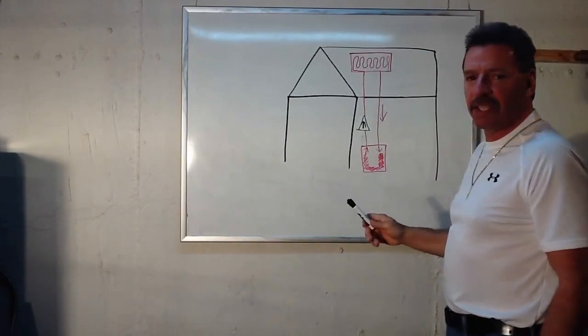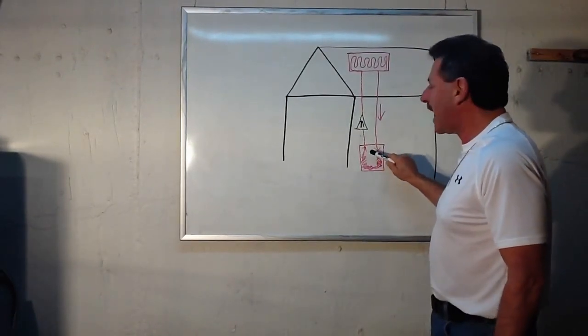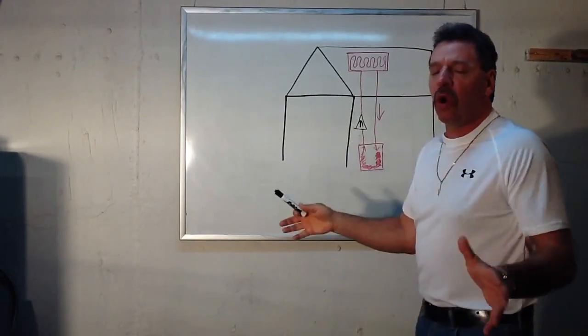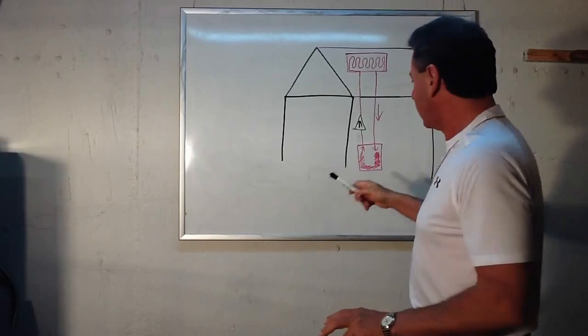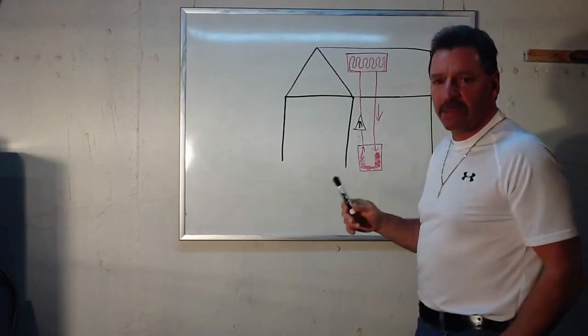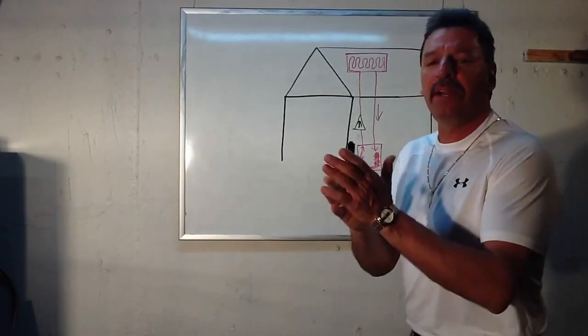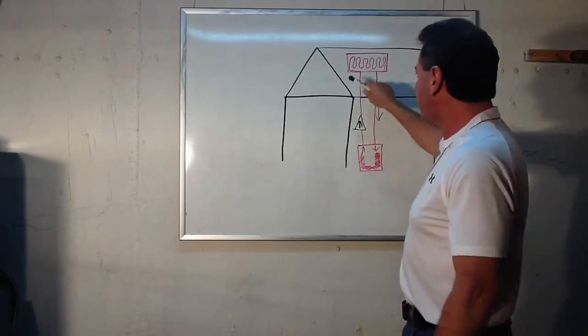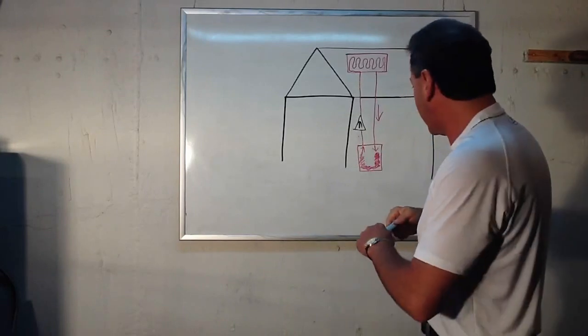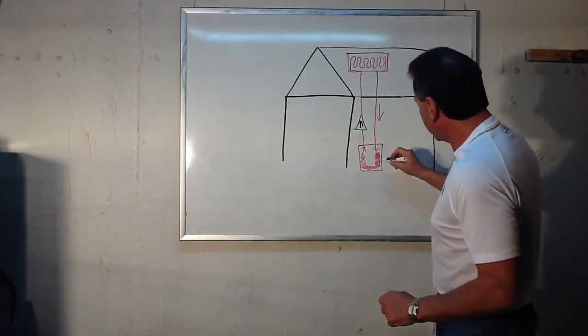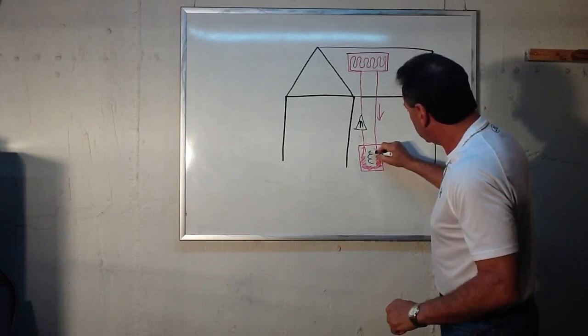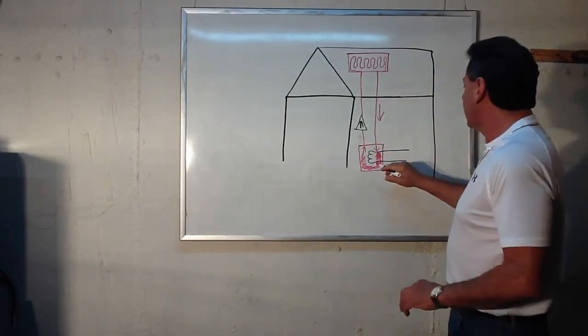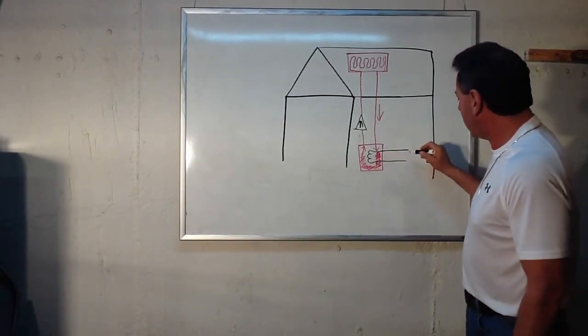But what's special about this heat exchanger is it has a second tank or a coil in it where the true cold domestic water that touches your skin goes into it and steals the BTUs and gets hot, but never actually touches the dirty glycol or the antifreeze. But it steals the BTUs from it and it gets hot. And that coil would look something like this inside that tank. So it's a coil inside the tank.